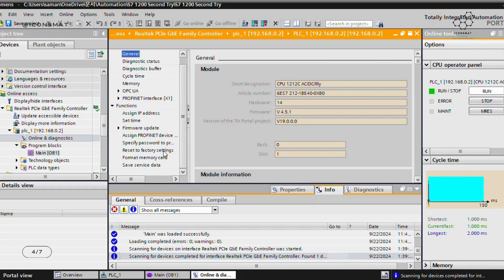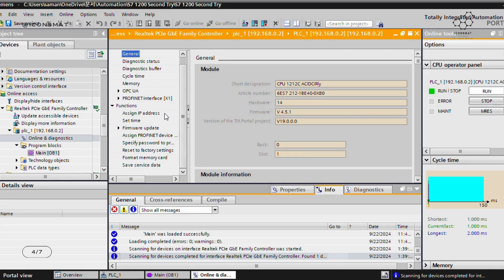Click on 'Reset to Factory Settings' and follow the prompts — you will be able to reset your PLC and all the lights should turn off. If everything is healthy, you should see just the RUN/STOP LED lit, which shows that the connection and program are healthy and good to go. If there are any other lights on, you should be suspicious that something may not be going well. You can also assign the IP address here — I've assigned 192.168.x.x.